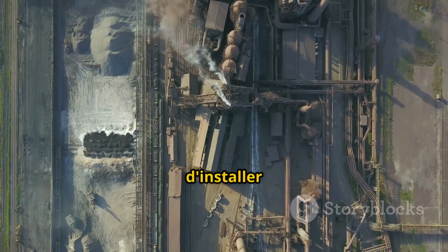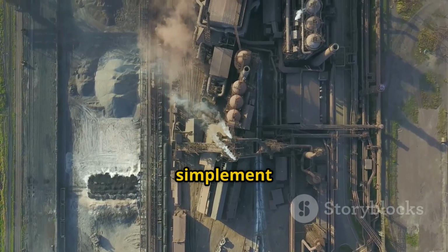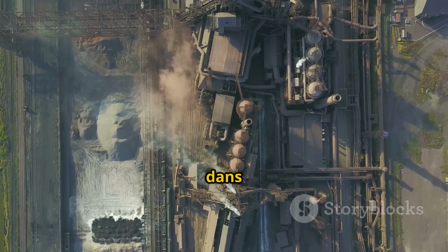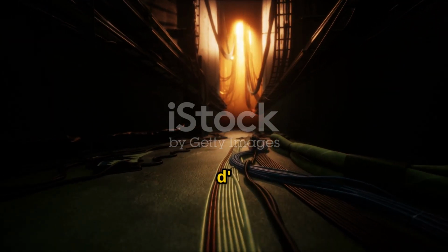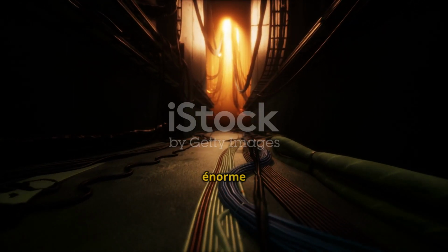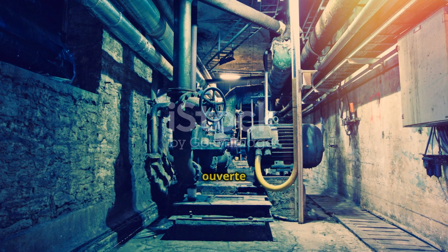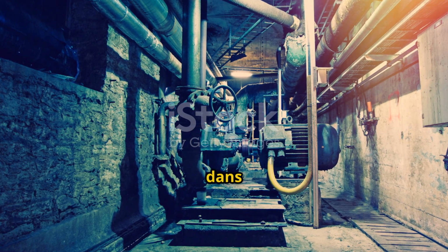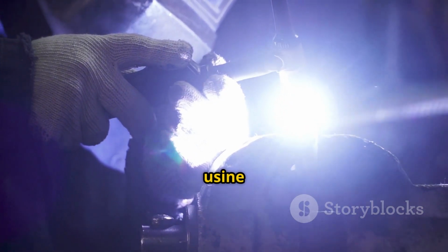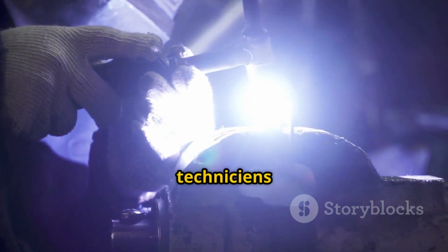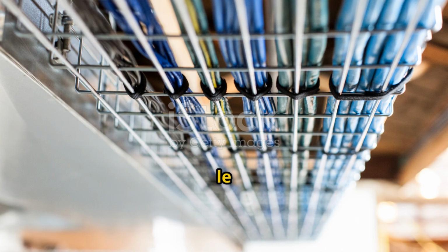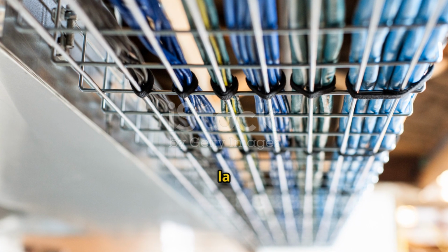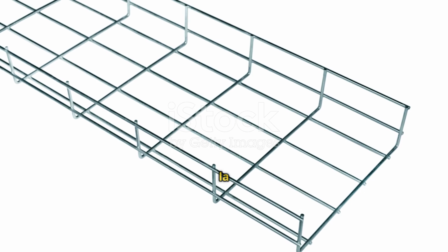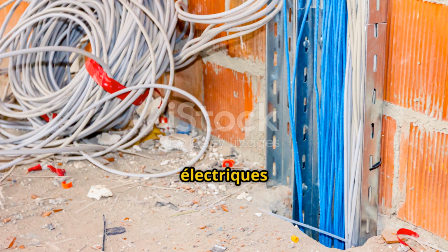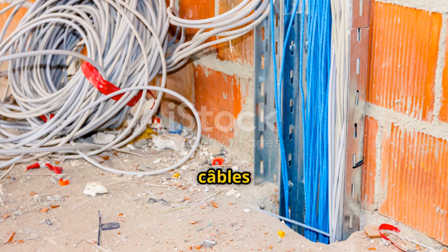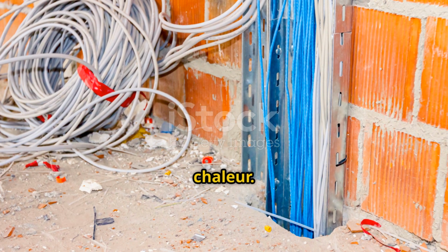Out of the practical challenges faced in the refineries and factories, a simple yet transformative concept emerged. Instead of enclosing cables completely within pipes, why not support them on an open, structural frame? This question led to the invention of the first cable trays. The earliest iterations were rudimentary, fabricated on-site by welding angle iron and flat steel bars. They looked like a simple ladder laid on its side. The ladder tray was born. It provided a strong, continuous support path for cables. Electricians could lay bundles directly onto the rungs, much faster than pulling them through conduits.